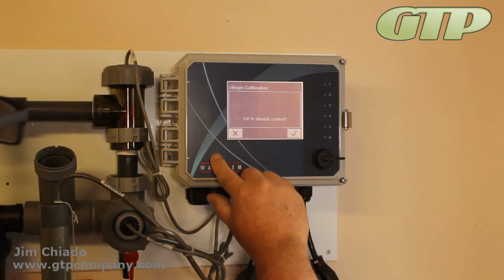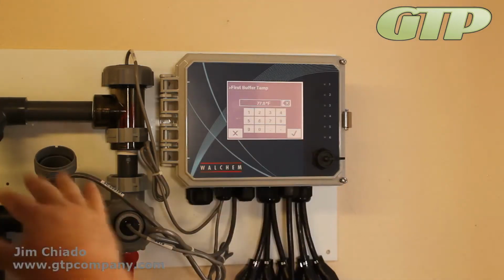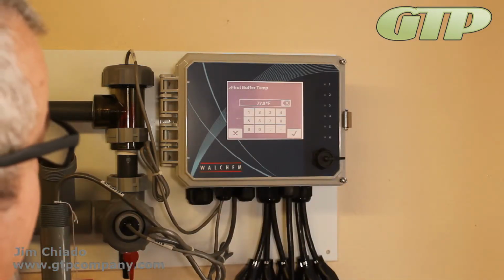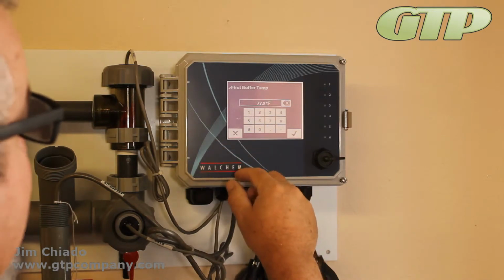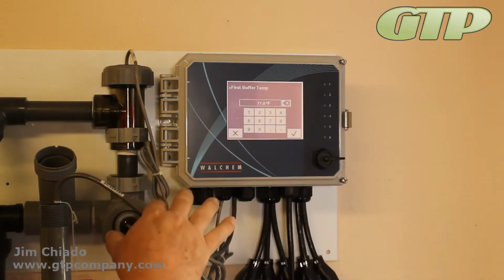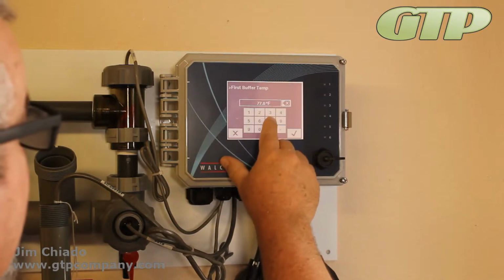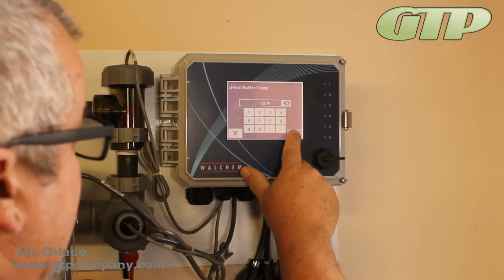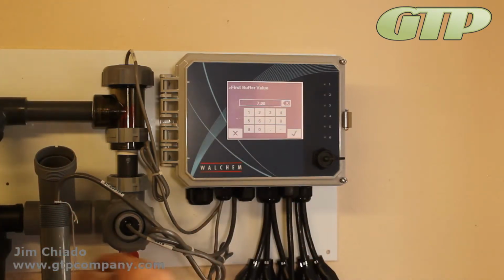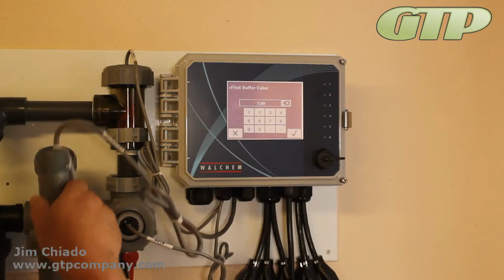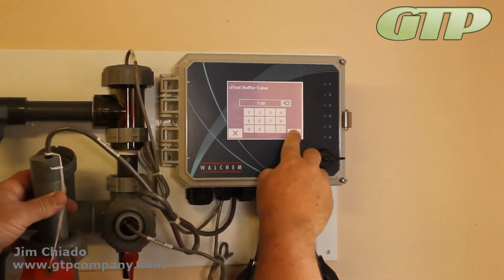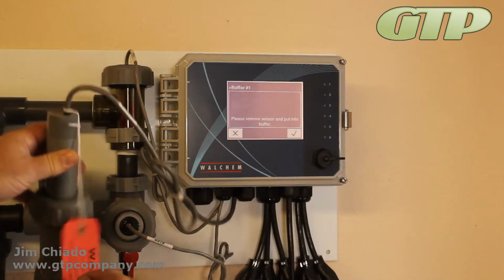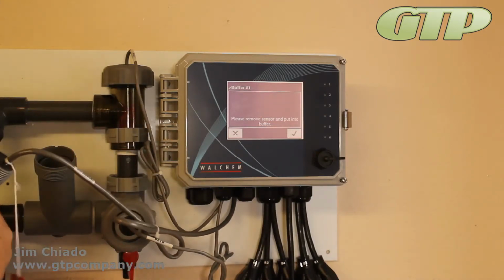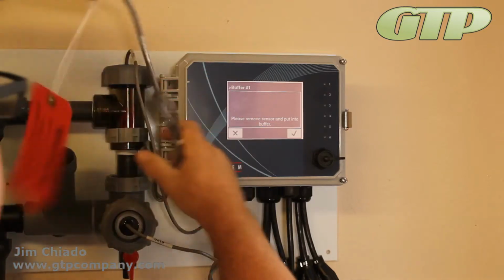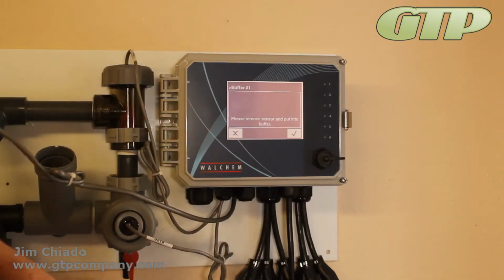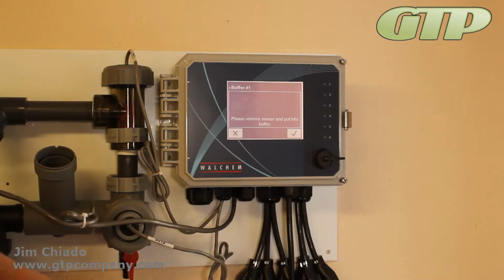Okay, so I'm going to do a 2-point calibration. I'm going to disable the control so that I don't want it to do any differences here. I'm going to tell it that the buffer temp solution is 77, because this doesn't have a temperature portion of it. We saw earlier that it's about 73 degrees, so I'm going to just change that a little bit. I'm going to put in the first value, which is 7. Actually, it's going to tell me in here to remove it from the thing. And I have it in my little custom T again. There we go, and put it in my 7.